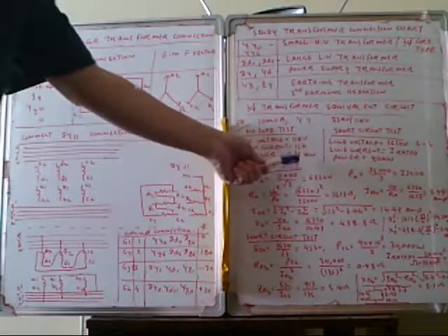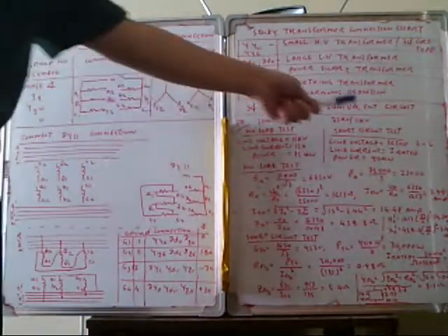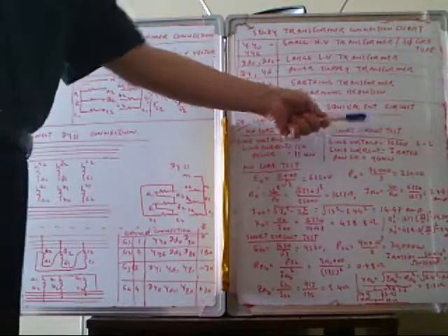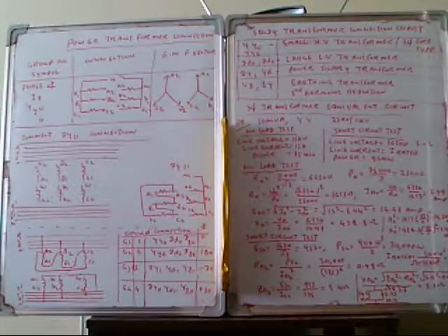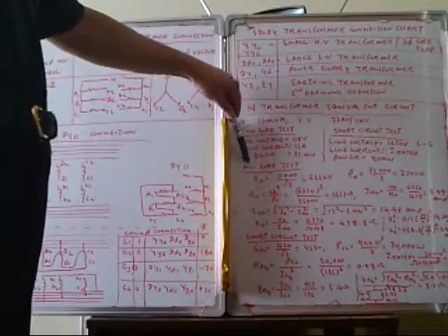So firstly, we do the no-load test. No-load test means that we supply the voltage at the low voltage side, and the high voltage side is open. Here the low voltage side is the secondary, so all values we get are secondary values. So this is for the low voltage side. Okay, so in the no-load test we can calculate.